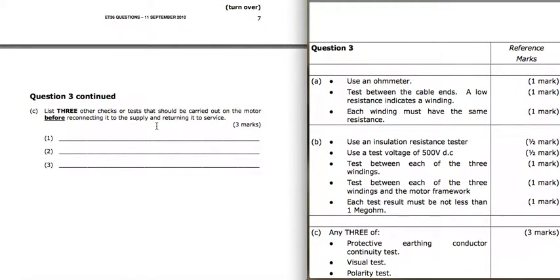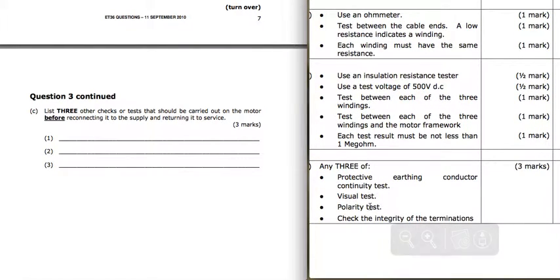3 other checks or tests that should be carried out before reconnecting it. So we're looking at protective earthing conductor continuity test, a visual test, polarity test, and checking the integrity of the terminations. So I'd be remembering those 3 there really. Your earthing, visual, polarity.